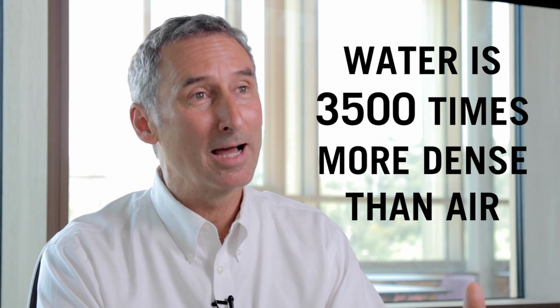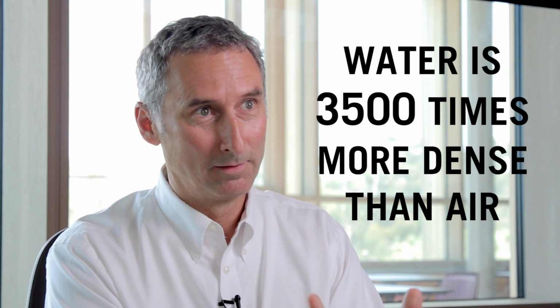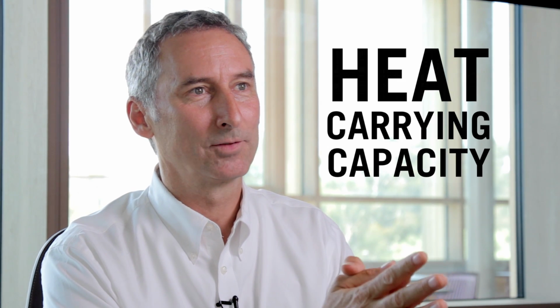The other thing that chilled beams take advantage of is that water is the medium for providing the heating and cooling. And so we have water that goes through the chilled beam, hot water or cold water, so that chilled beam can do heating or cooling. Well, water is much more dense than air. It's 3,500 times more dense than air when we talk about the heat carrying capacity.